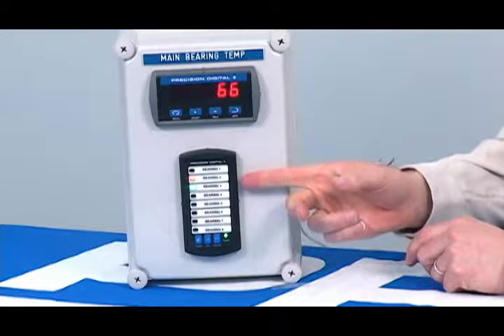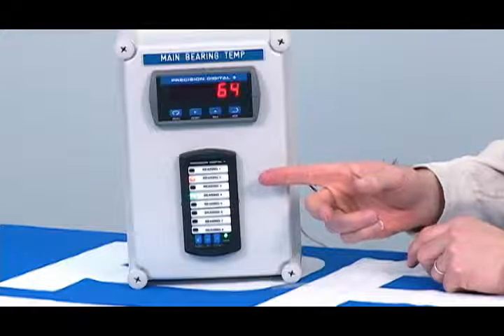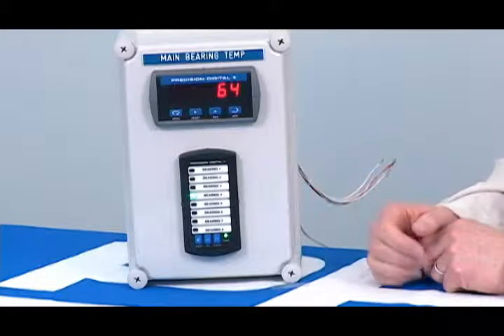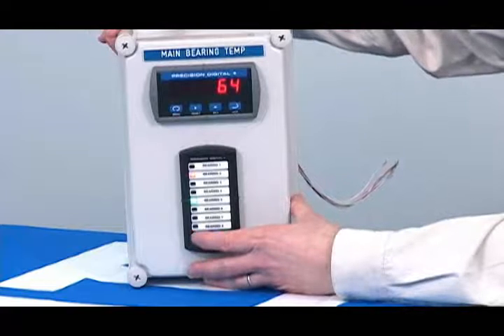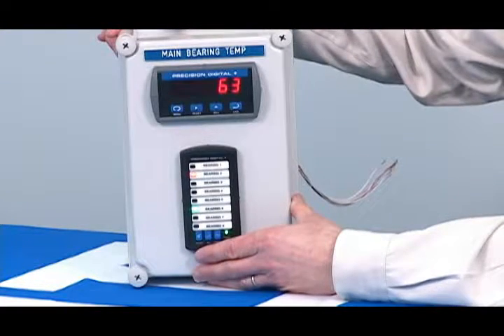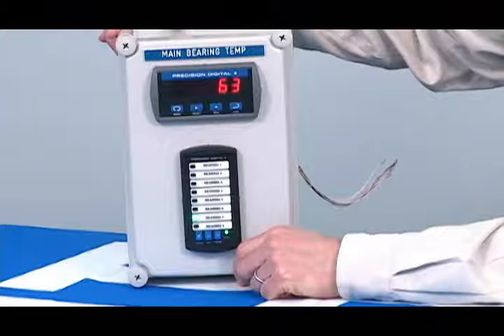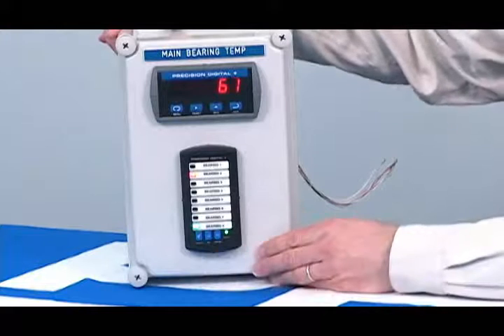And you can see the light flashing, the built-in horn sounds, and also a relay transfer that could be used to drive another light. The Minimux continues to scan. I press the silence button, and the horn silences. But the light will keep flashing until I press the ack button, and then it will go out again.